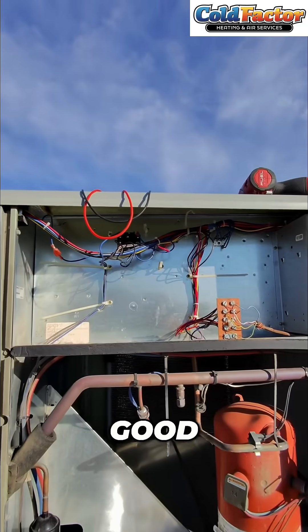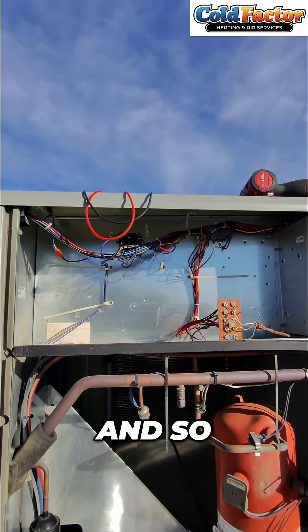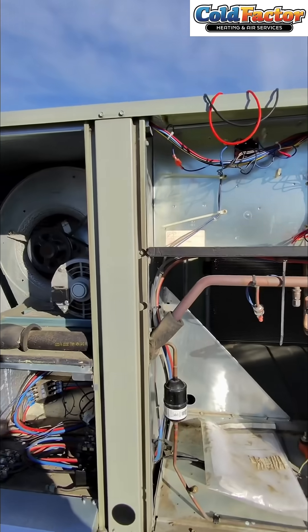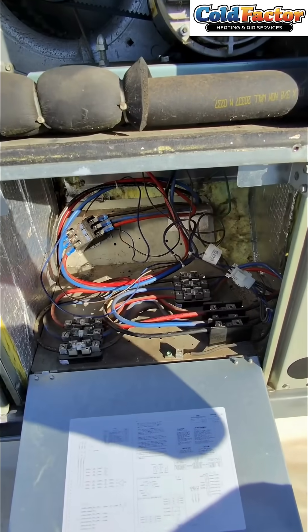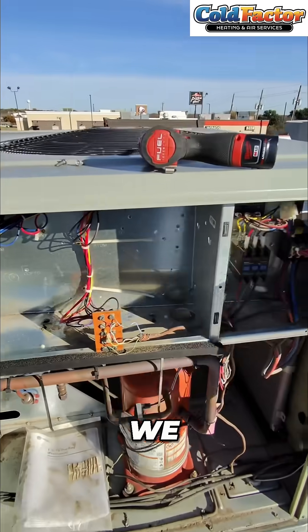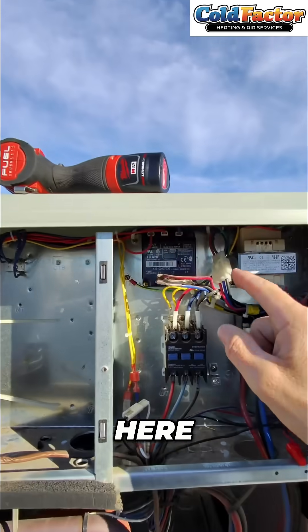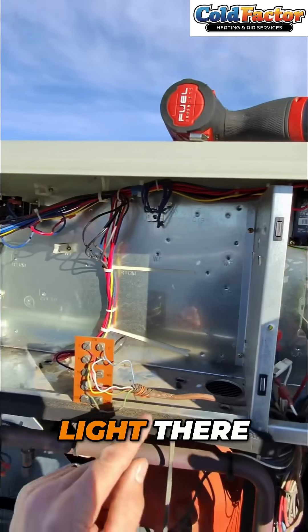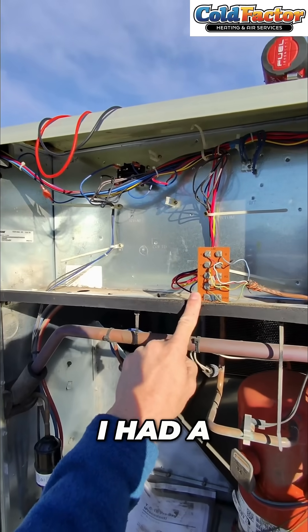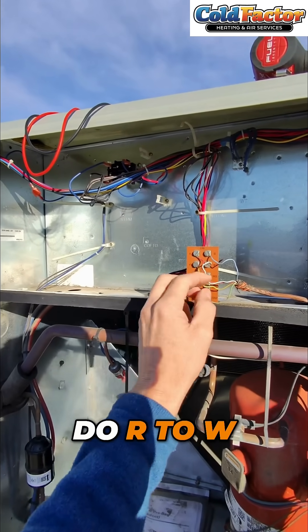What would you think would make this system work or not work? We do have 24 volts present — that has been established. We checked here and got a good light, so the transformer is good. I had a technician do R to W but nothing would work.